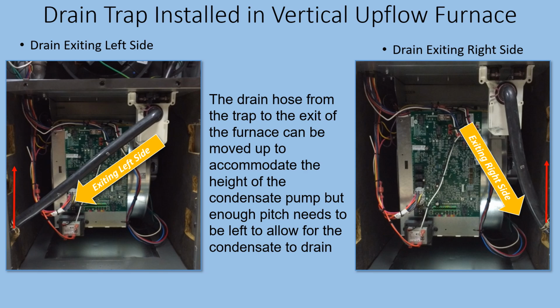And drain trap installed in vertical upflow furnaces, you can drain exiting left or right. The drain hose from the trap to the exit of the furnace can be moved up to accommodate the height of the condensate pump, but enough pitch needs to be left to allow for the condensate to drain.